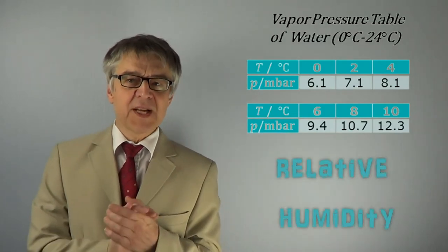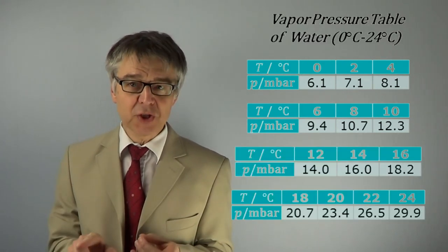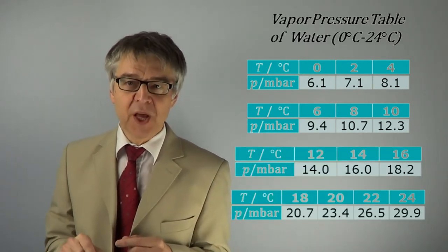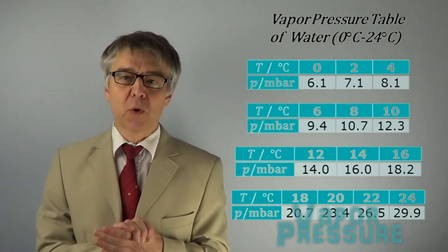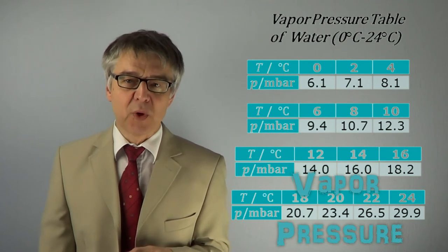The degree of saturation of the moist air we can calculate by dividing the partial pressure by the vapor pressure. Here we see a vapor pressure table of water, which you can calculate, for example, with Antoine's equation.